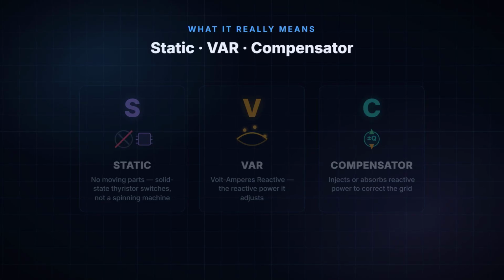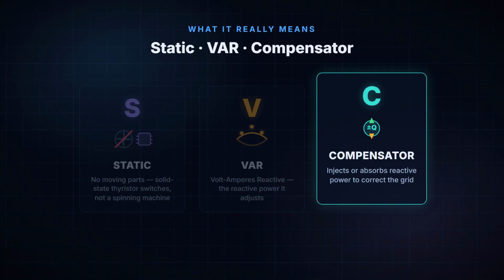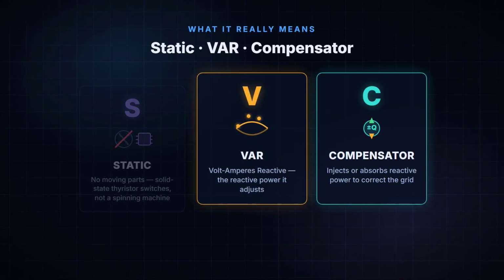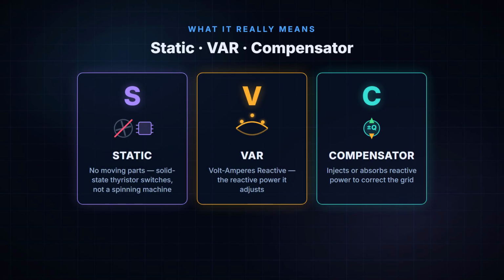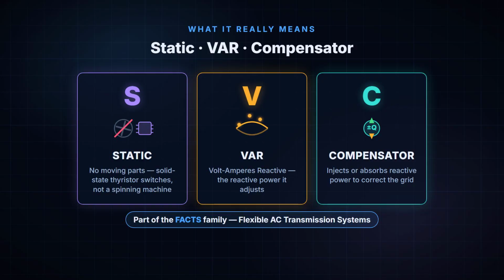So, a static VAR compensator. Let's take the name apart, because it tells you exactly what it does. Compensator. It compensates, it corrects, by injecting or absorbing reactive power. VAR, that's the reactive power we just talked about, the thing it controls. And static, this is the clever part. Older systems used a spinning machine called a synchronous condenser to do this job. An SVC does the same thing with no moving parts at all, just capacitors, reactors, and fast electronic switches called thyristors. It belongs to a family of devices engineers call FACTS, flexible AC transmission systems, and its job is simple to state. Keep the voltage steady by adjusting reactive power instantly and automatically.